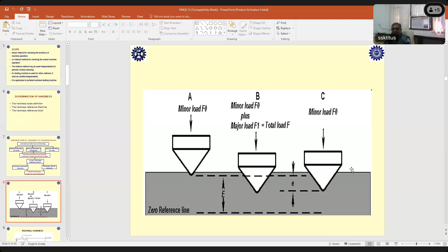Now, after measuring the E, you have to subtract it from 100 for certain scales, and you have to subtract it from 130 for certain scales. There are different scales. I told you it has a very large spectrum. The large spectrum basically comes from the kind of indenters and the different forces you are applying on the sample. Now let us look at the timing cycle a little bit.